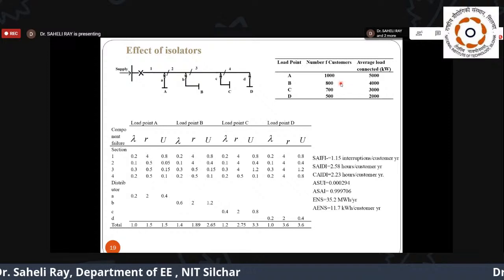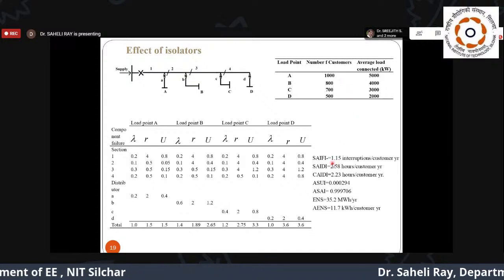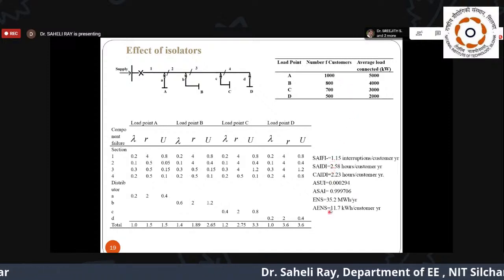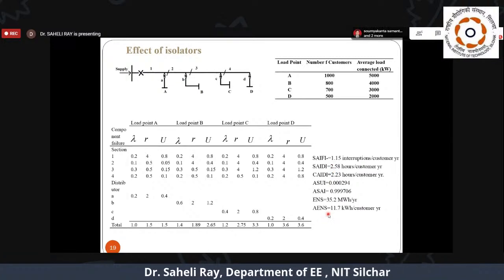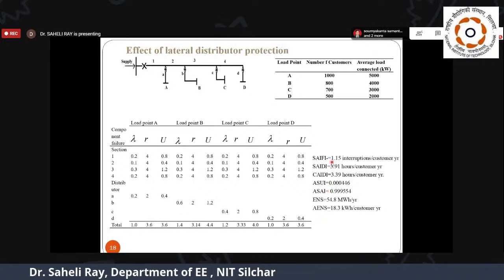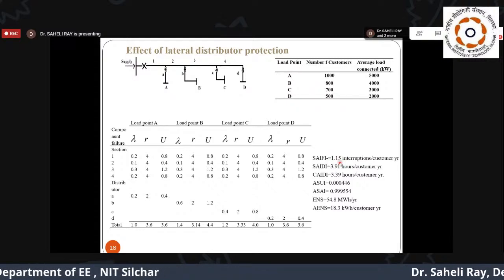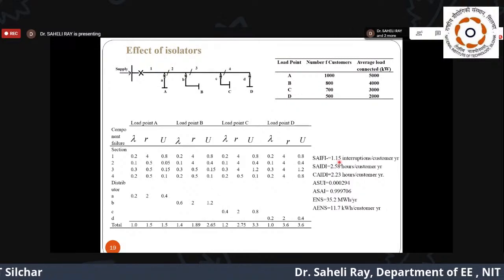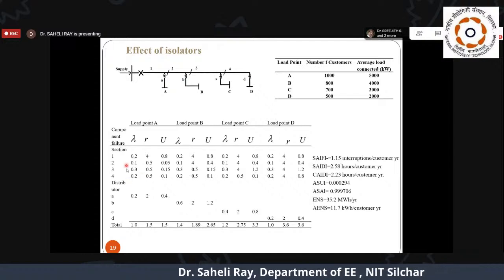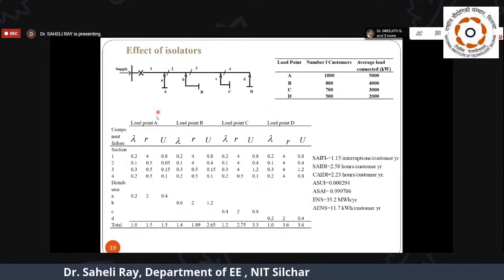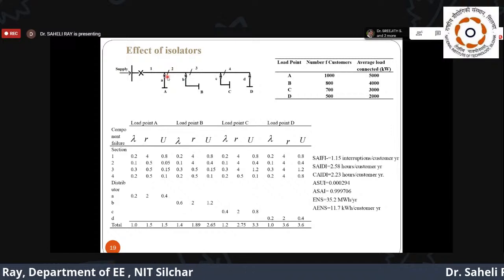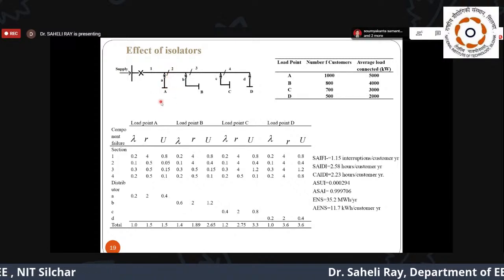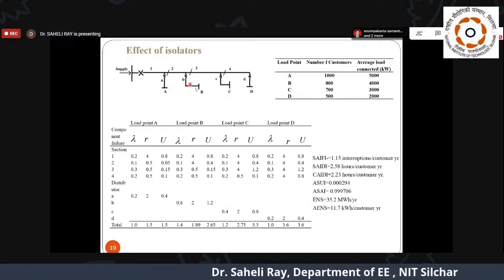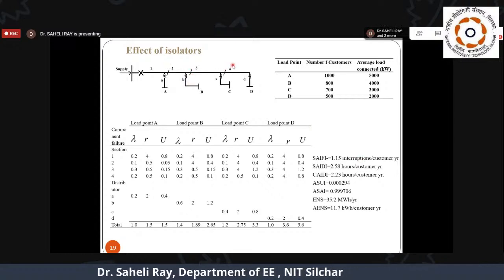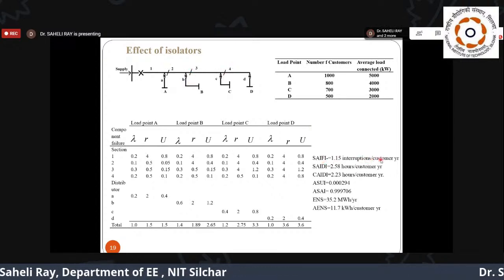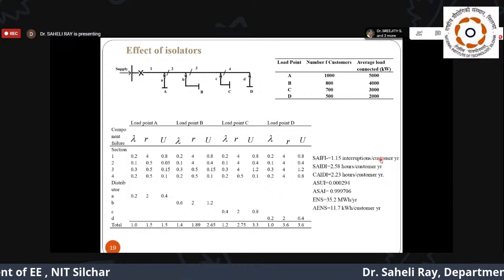Now again, if we use the same formulae, we can find the SAIFI, SAIDI, and all these indices. We can compare them with the previous indices. You see the SAIFI will remain the same. In the previous index also it was 1.15. Here also it is 1.15. Why? Because the failure rate is not changed. It cannot stop the occurrence of a fault. Instantly it will be interrupted. So the number of interruptions cannot be changed by incorporation of some extra isolators in the system. So the SAIFI will not get changed, but there will be a change in the SAIDI.